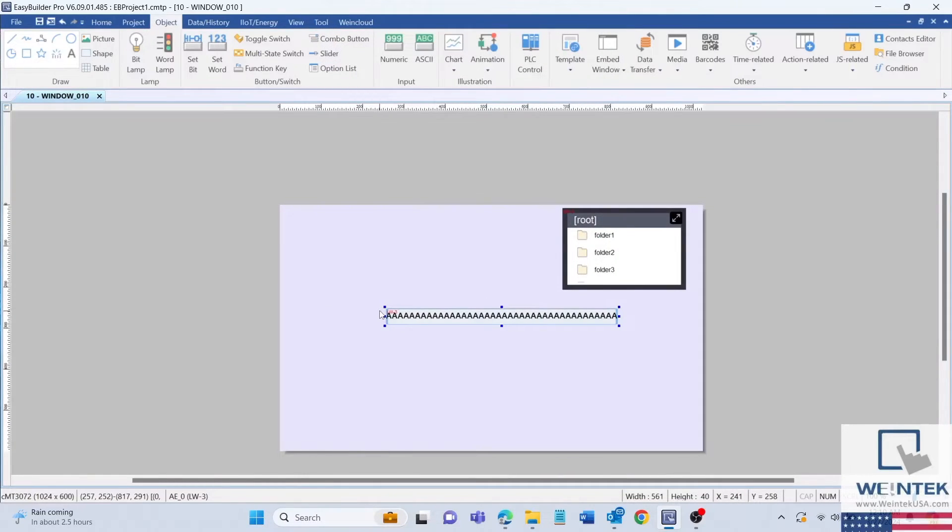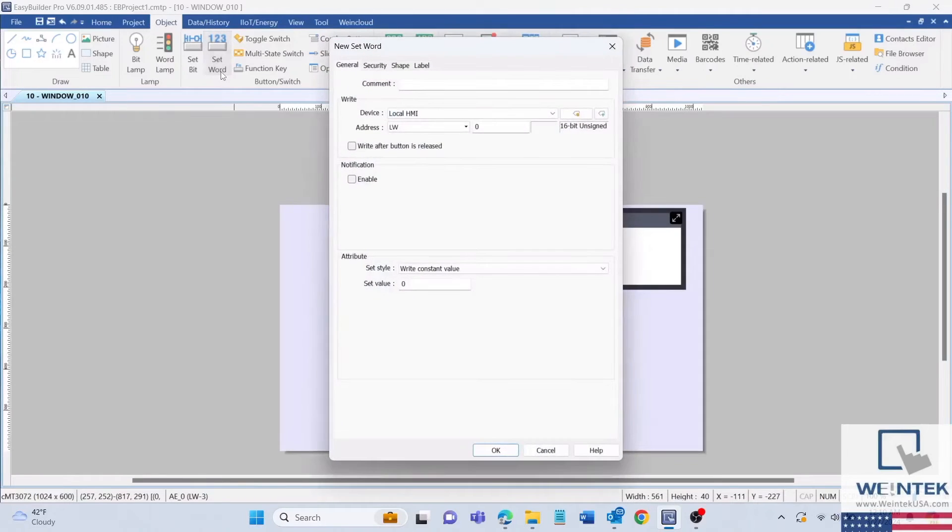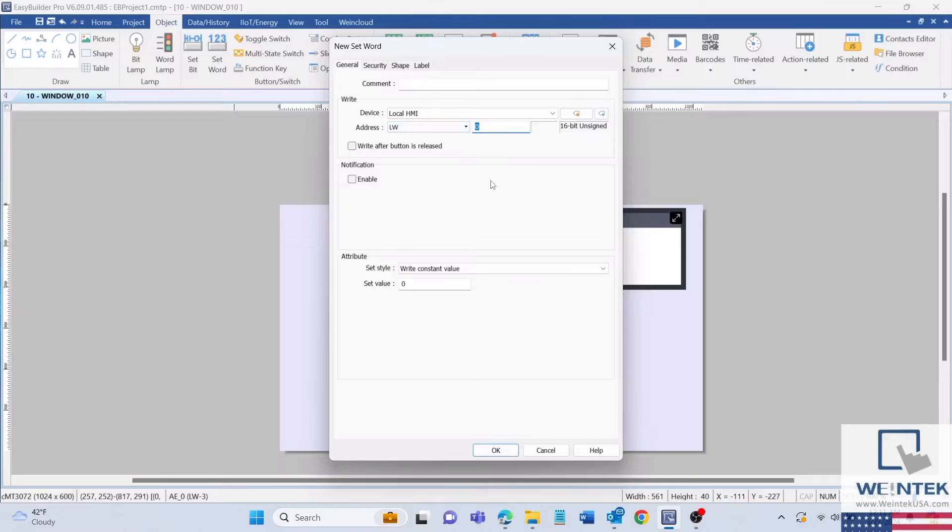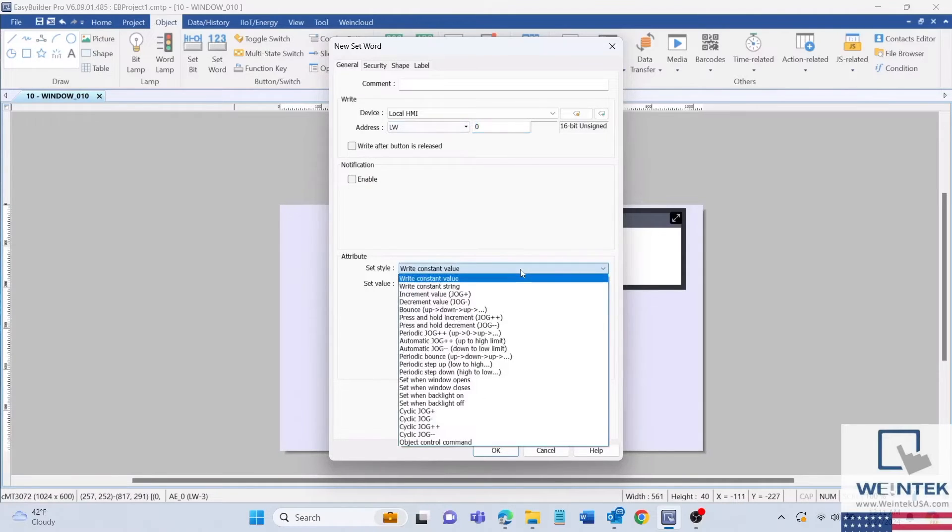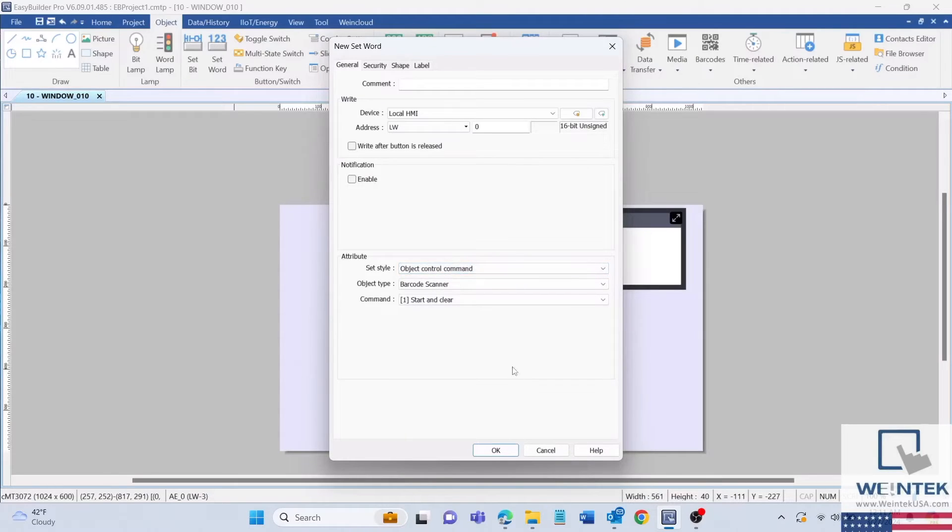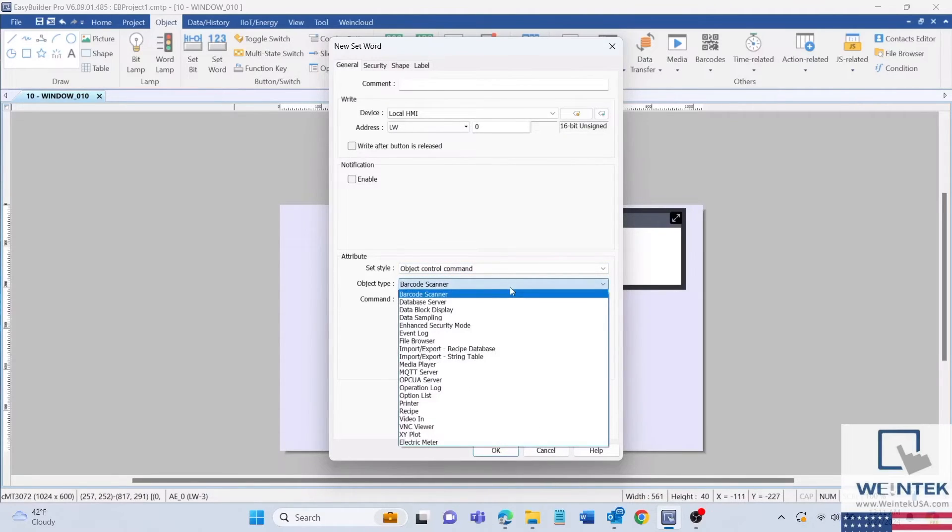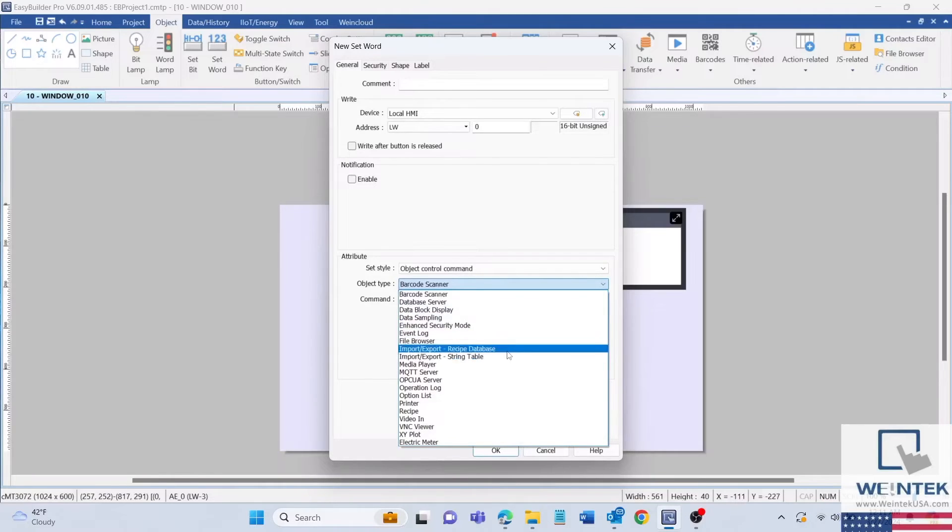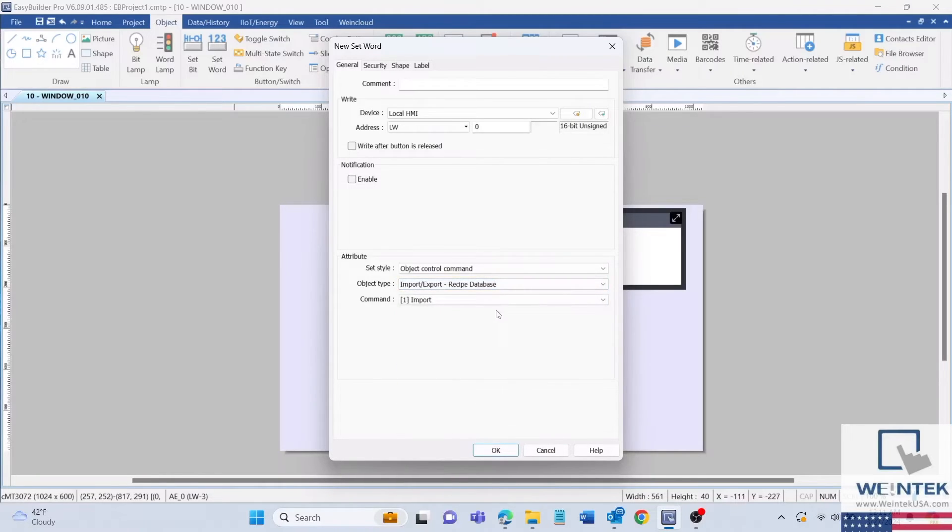Now we will need to create two command buttons for importing or exporting a recipe file. Start by selecting a set word object. The write address will be LW0 for me since that is the import/export object control address. Then select object control command for a set style. Set the object type to import/export recipe database and set the command to import.